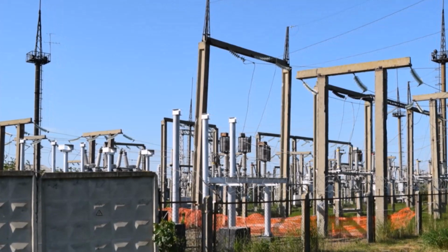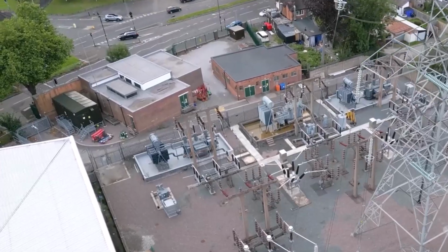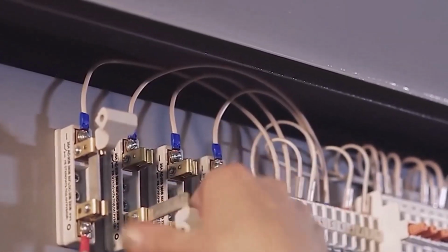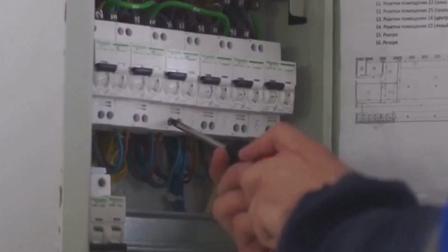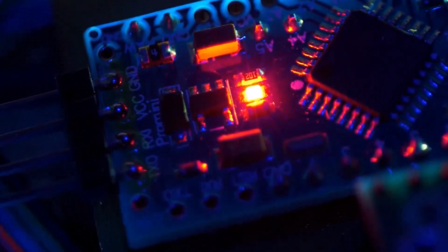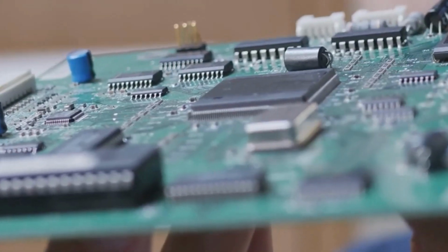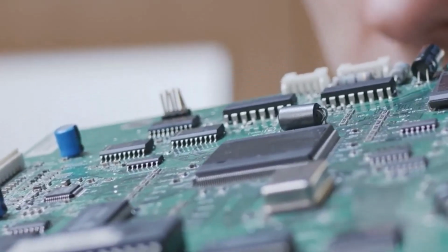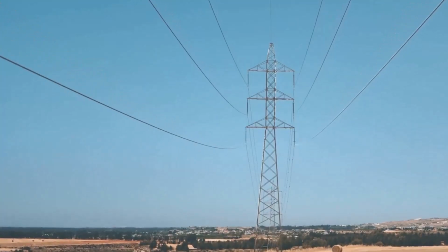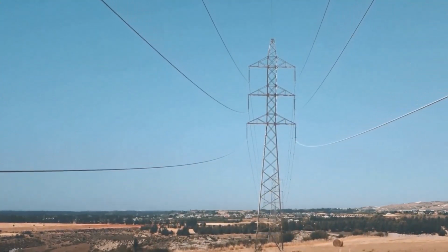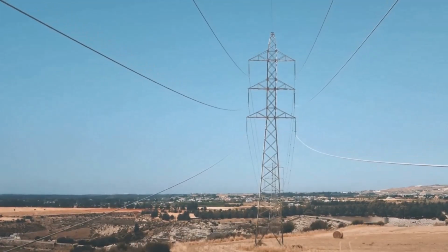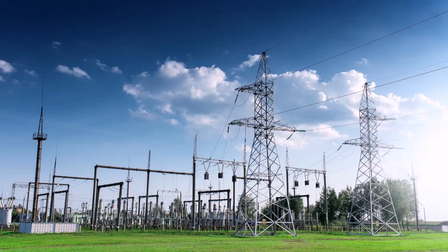Of course, no system is perfect, and the Y connection has a couple of disadvantages. A major one is its reliance on the neutral wire. If the neutral connection is lost or broken, the system can become very unstable, especially if the loads are unbalanced. Without the neutral to keep things in check, the phase voltages can fluctuate wildly, with some becoming dangerously high and others dropping too low. This can easily damage or destroy sensitive electronic equipment. Another drawback is simply the need for a 4th wire. In some applications, like long-distance transmission lines, the cost of an extra conductor can add up, making a 3-wire system more economical.